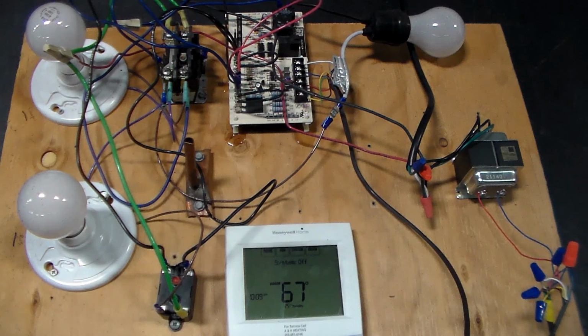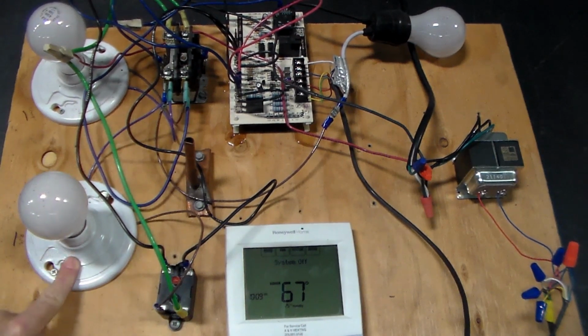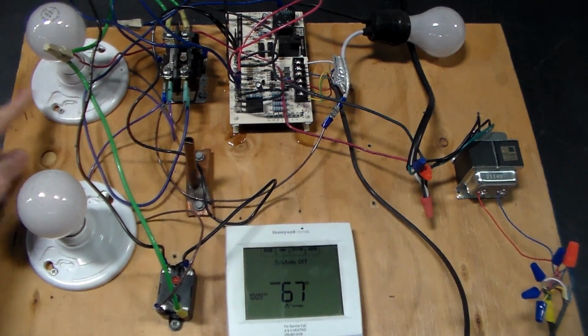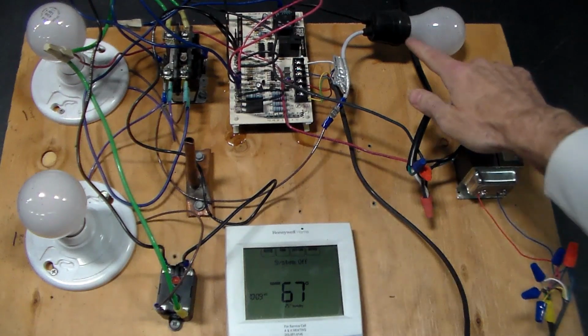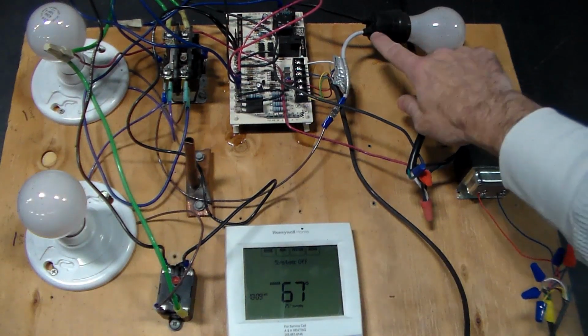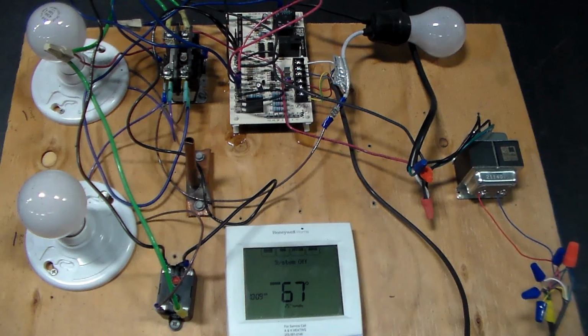I want to start with what we have here: a reversing valve right there. This one's labeled compressor, and this one over here is the outdoor fan, the condenser fan. We can see when we run normal mode, we'll start with cooling mode, because cooling mode with this typical board, non-Ruud board, is going to actuate the compressor, the condenser fan, and the reversing valve. Everything's going to pop on.